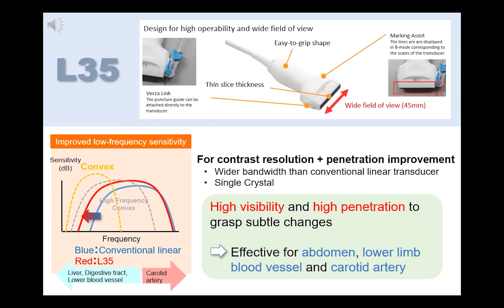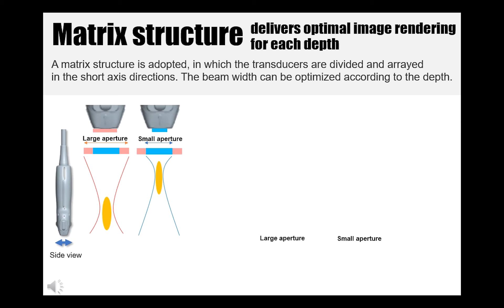This slide shows another element that achieved the goal of a linear probe for abdominal examination. We have adopted a matrix structure in which the transducers are divided and arranged in the direction of the short axis, that is, the thickness of the probe. This matrix structure allows for optimal image rendering according to depth. It is designed to optimize the beam width according to the depth. This makes it possible to select the optimal short axis aperture according to the depth, and thus to produce images suitable for each region. This is the reason why this probe has succeeded in achieving high image quality.